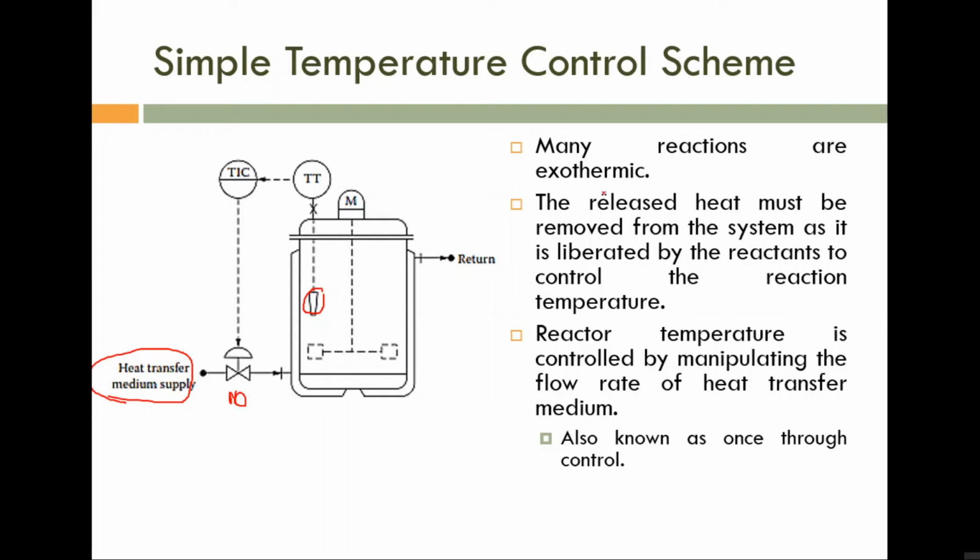If it is an endothermic reaction, then we have to use a normally closed valve. So please note, if it is an exothermic reaction, we have to use a normally open valve. Okay. So now we are going to select a controller. Anyway, it is normally open.